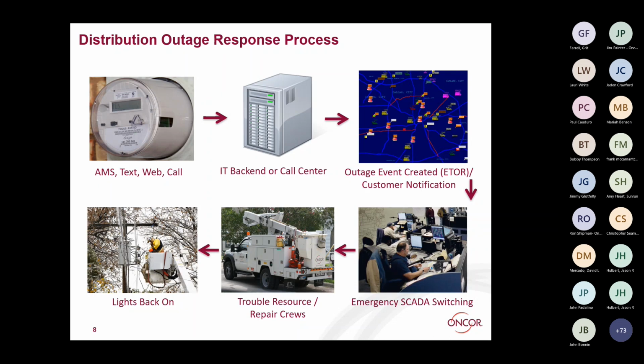Having historical interval data and these measuring points opens up a whole new area for predictive analytics around equipment performance, like when a transformer fails or is overloaded. We even have a high-level load flow estimator on the distribution system that uses old load information, the load profile per meter, to estimate current load flow based on what happened 12 or 24 hours ago. So you get a more accurate understanding, but it's still not anything near a true SCADA system - much better, with a lot of operational advantages, but not to the same degree.